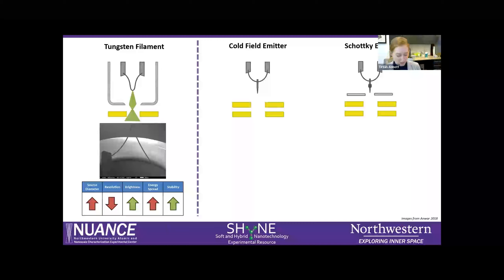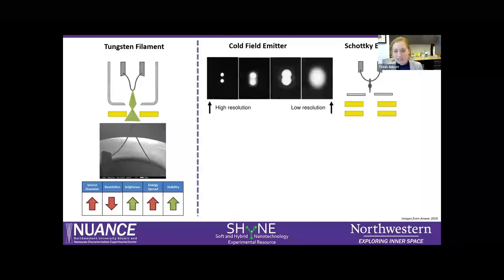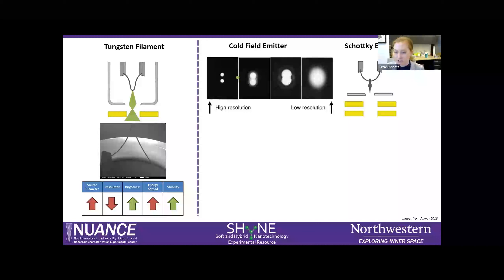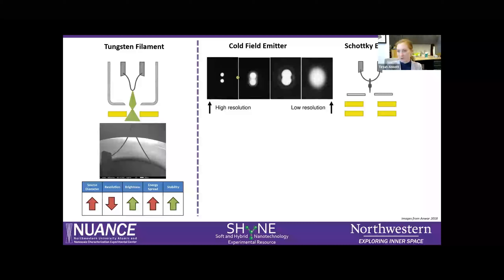In the SEM, resolution refers to the ability to resolve or differentiate two points. To achieve the highest resolution, you want your probe to be as small as or smaller than the smallest feature you want to analyze. Tungsten thermionic sources get changed about every 100 hours, so their lifetime is not very long compared to field emitters.